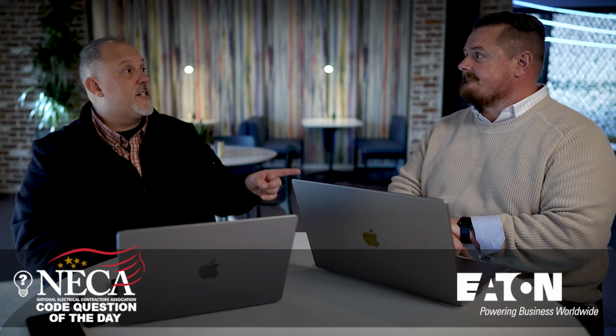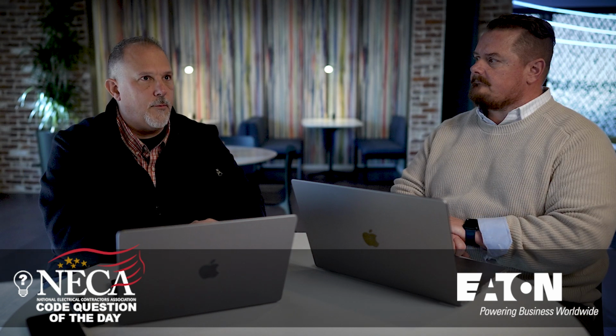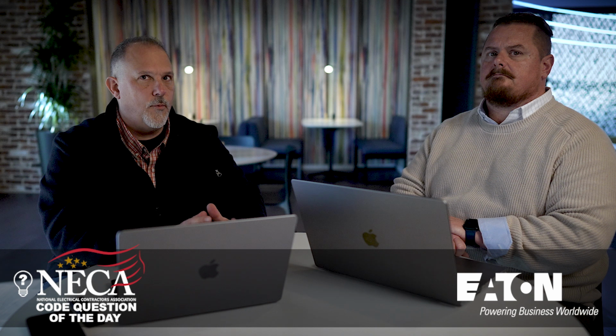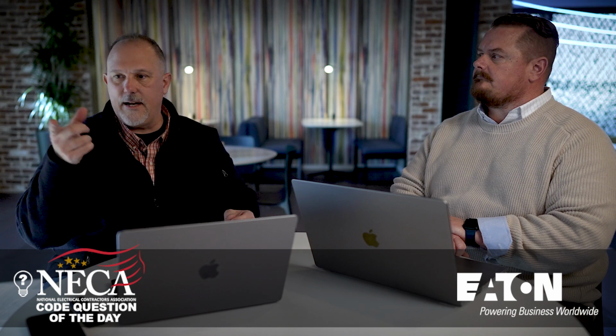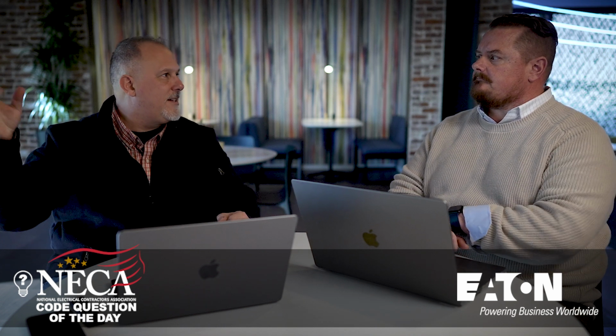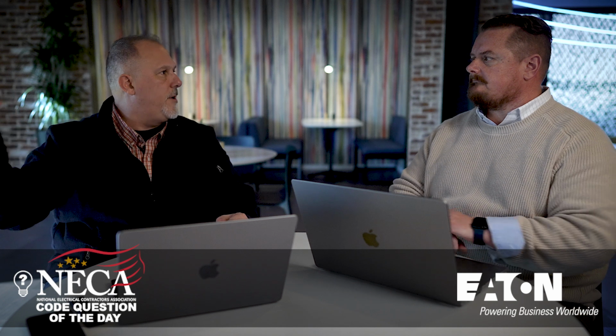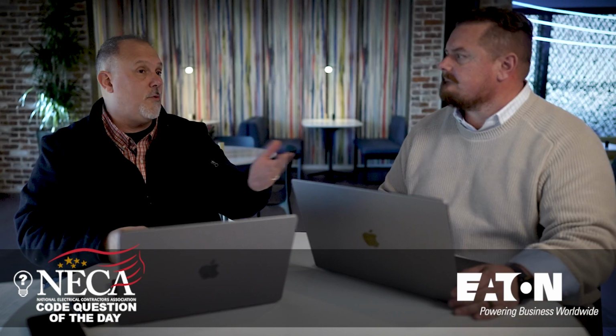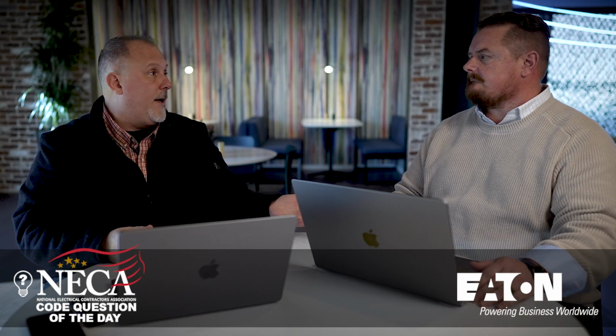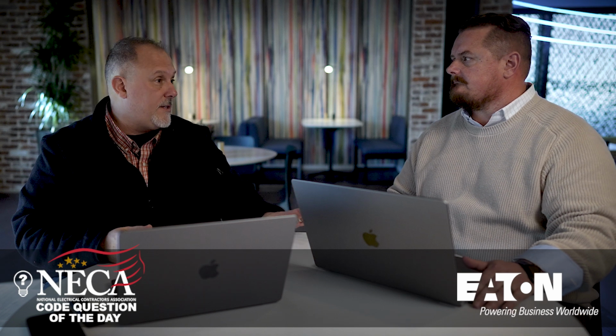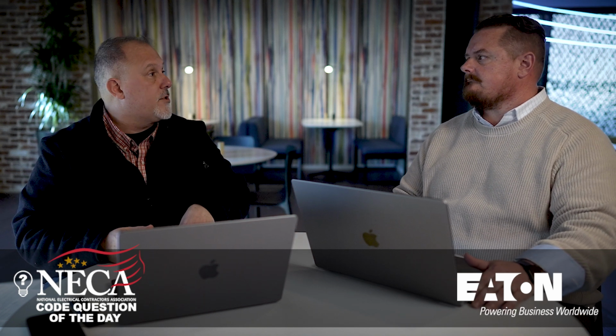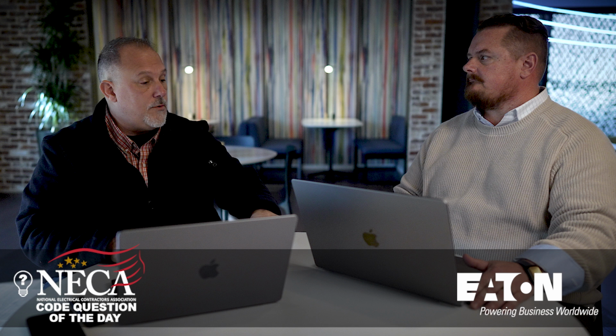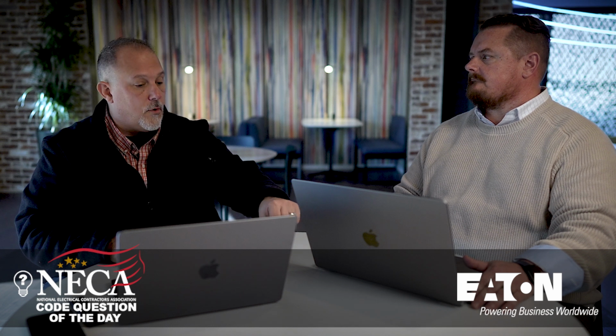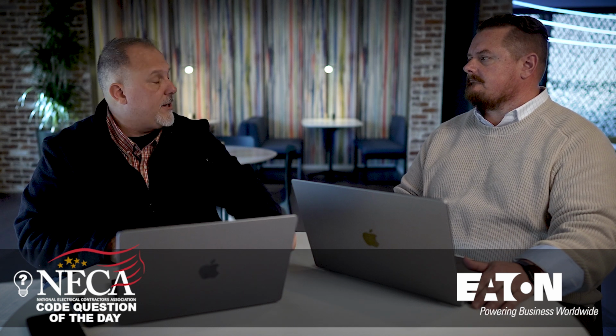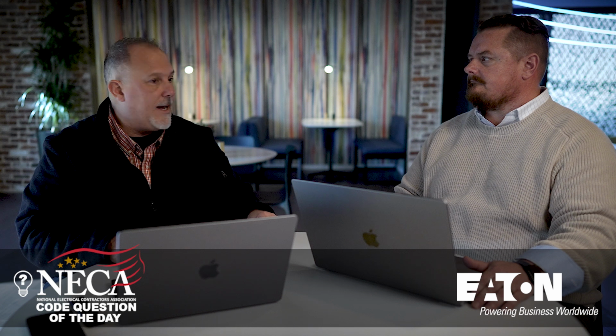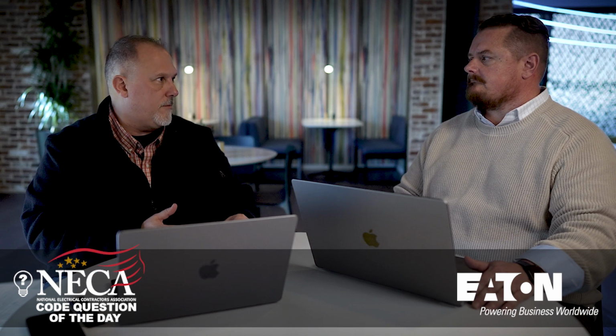Yeah. Now, the challenge that we have, when you think about calculating fault currents, we don't calculate it down to a receptacle. We calculate it down to your main distribution equipment, your panel boards. Industrial control panels are even further down the line. And I can tell you honestly, I have never done a short circuit study that went down to an industrial control panel or to the elevator control panel or things like that. I hit all of the major distribution, right?